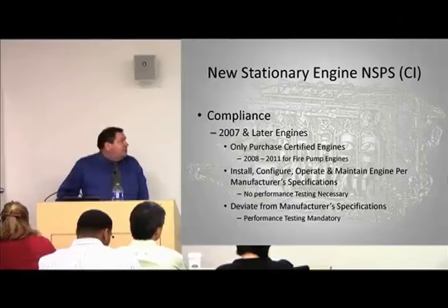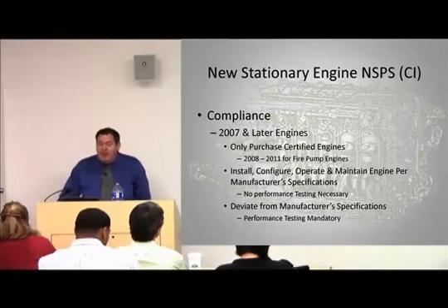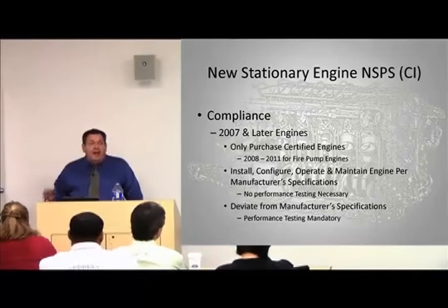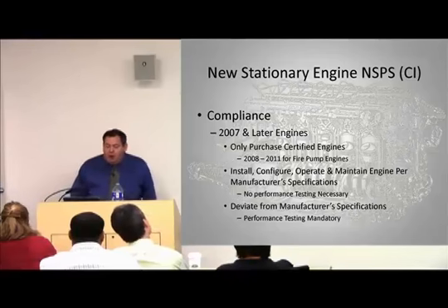So here's what compliance looks like. For 07 and later engines, only purchase certified engines. And if it happens to be a fire pump engine, 08 to 011, depending on the size of the engine and when it's phased in. If you buy a certified engine and you install, configure, and use that engine as the manufacturer designed, no further requirements are necessary. You're good to go.